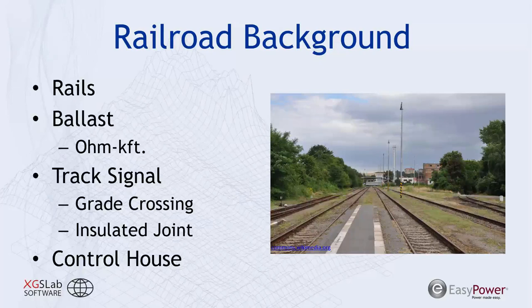And another thing I want to mention too is along track signaling, they may have insulated joints along a railroad. And these are points of the railroad that have a high impedance path so that the track signaling won't propagate from one track block to the next. And that helps with the train control system. But looking at it from an AC interference perspective, you could have peaks of voltage at those insulated joints. For example, if you had a parallel length of railroad that was inducing, that received or was induced, had 25 volts of induced voltage upon it, that 25 volts may be positive at one point of the insulated joint, and on the other half of the insulated joint, it is negative 25. So you have a total difference of voltage across that insulated joint of 50 volts.